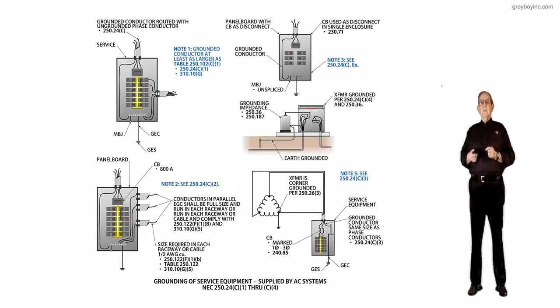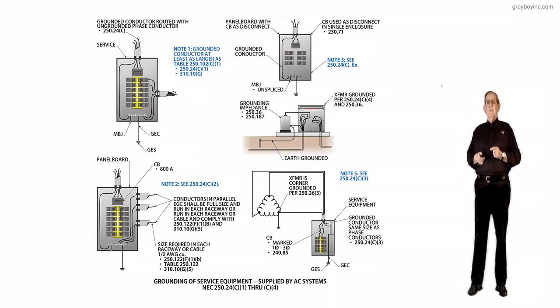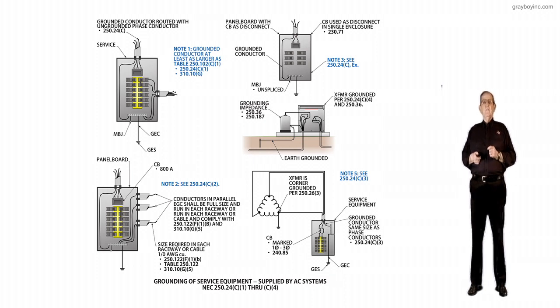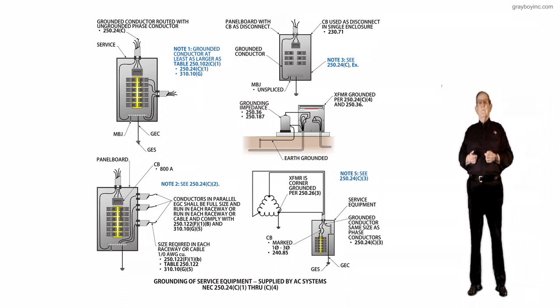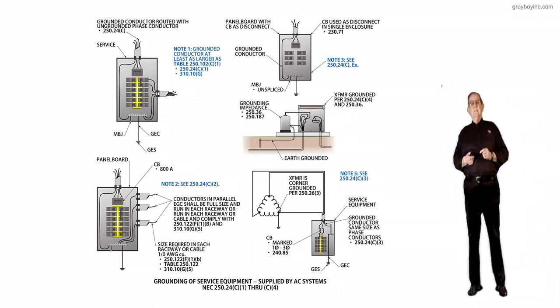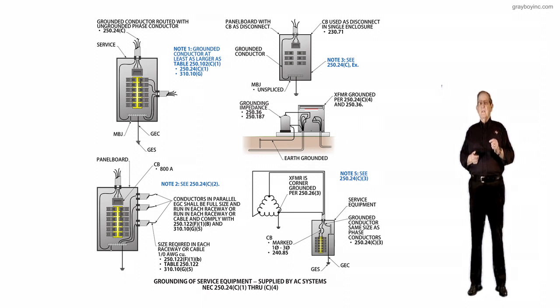And then if you notice the panel board to the left at the bottom, we're in parallel there. Say that you had a 600 amp main and your grounded conductors are in parallel there, they have to be 1/0 or larger. Now, we know that's in 310.10(H) and (G), and notice it's stated there, conductors connected in parallel. And the equipment ground should be full size, run in each raceway or cable, and has to comply with 250.122(F)(1)(b) if it's connected in parallel, and 310.10(H)(5) and (G). Now, notice that it's full size, but it doesn't have to be 1/0 or larger. It could be sized strictly by Table 250.122.